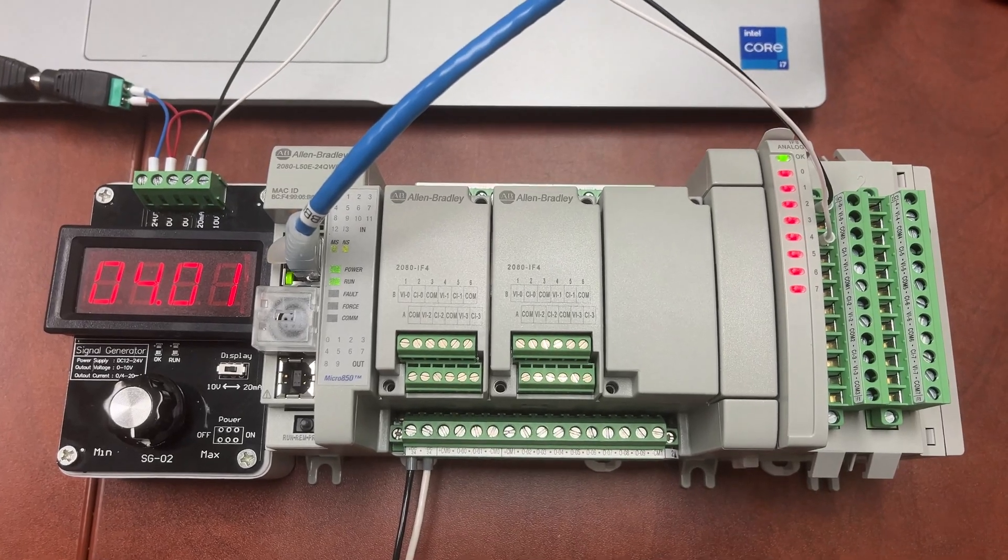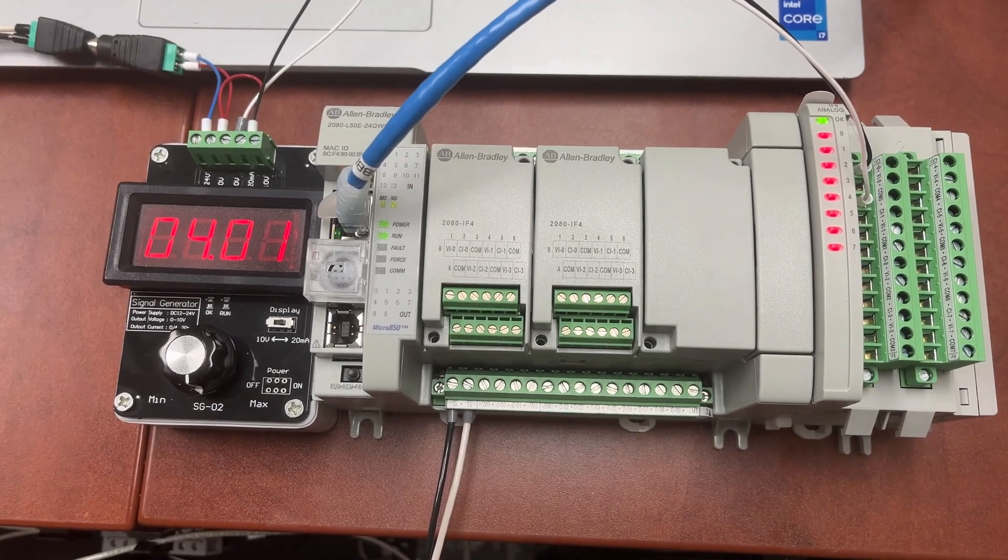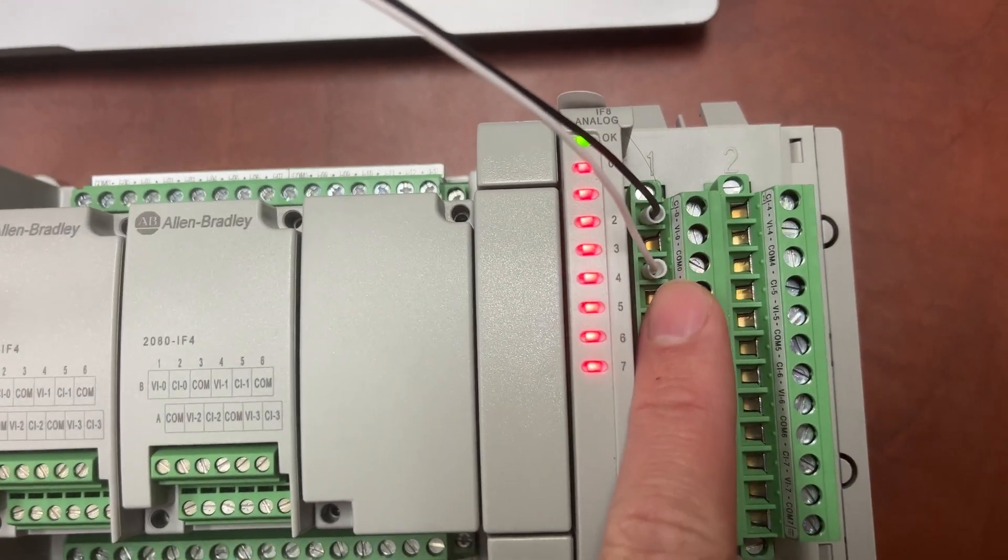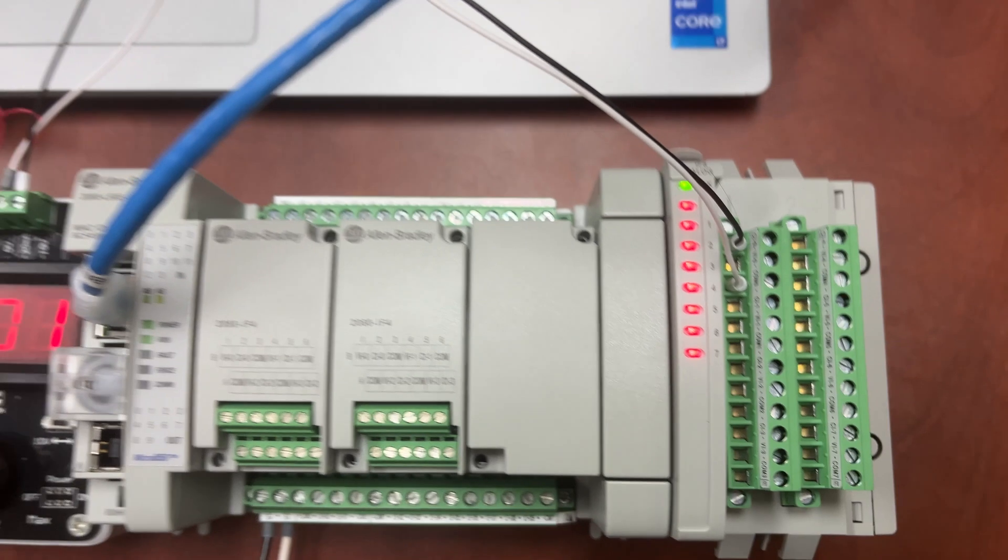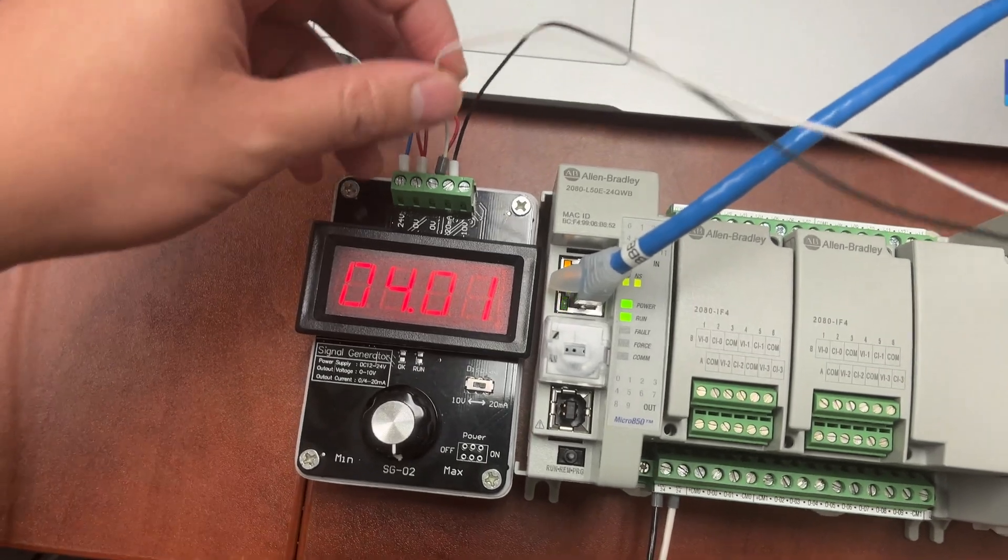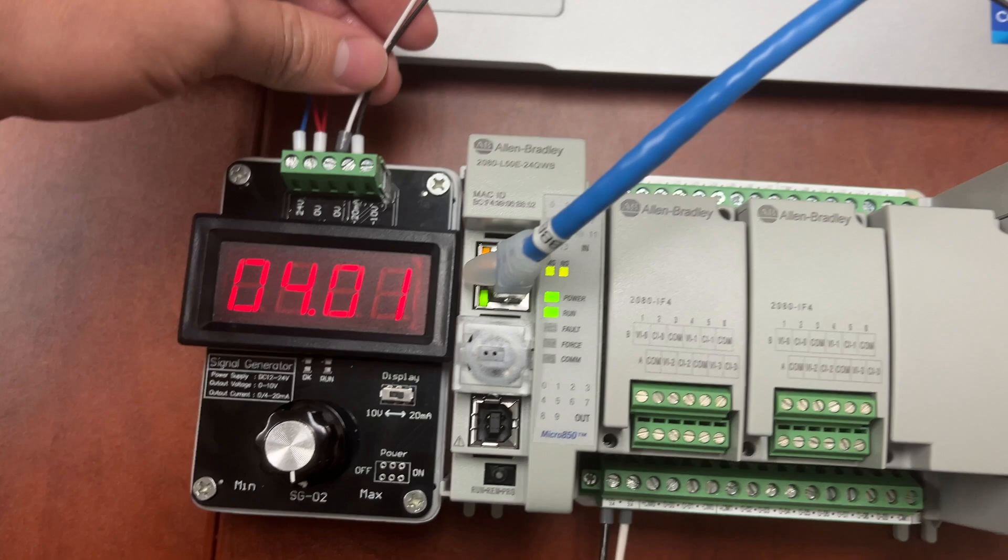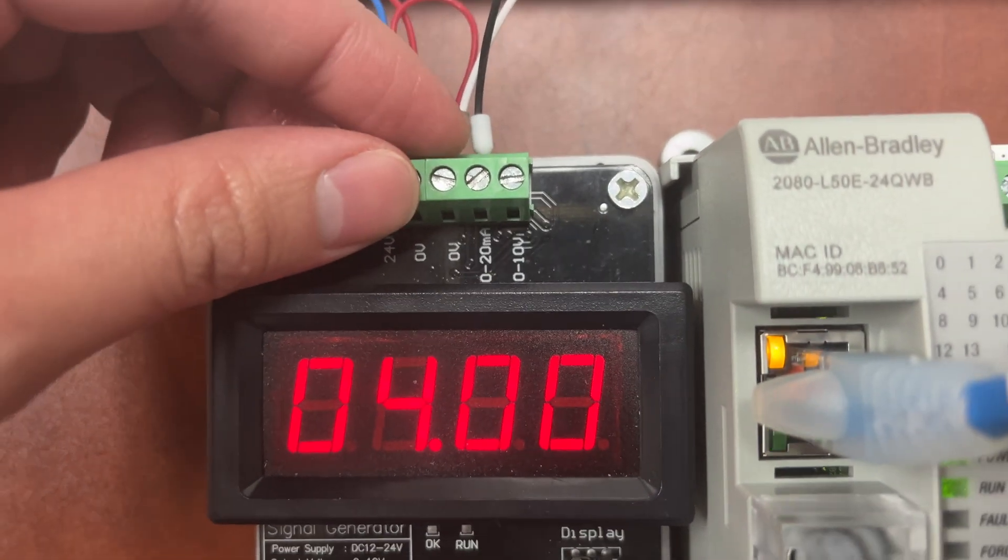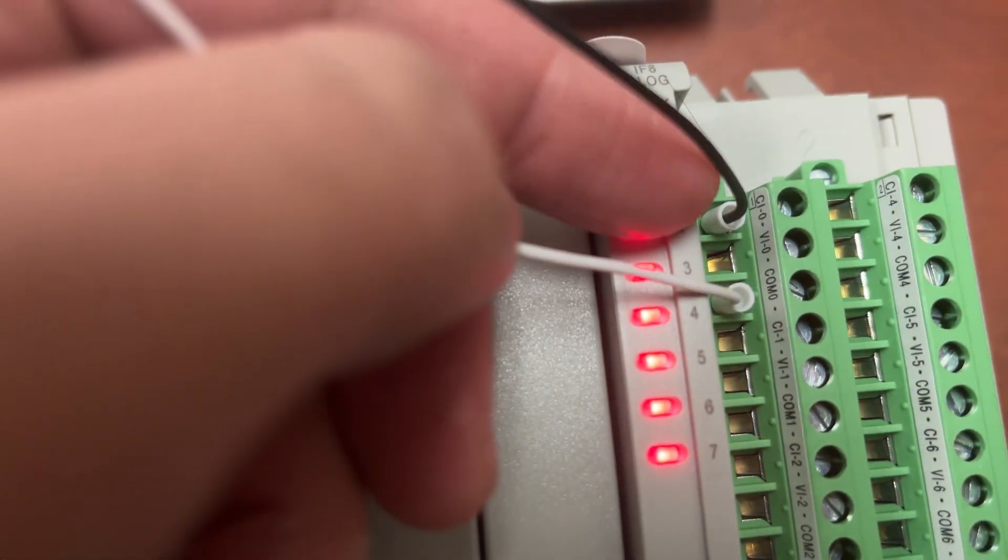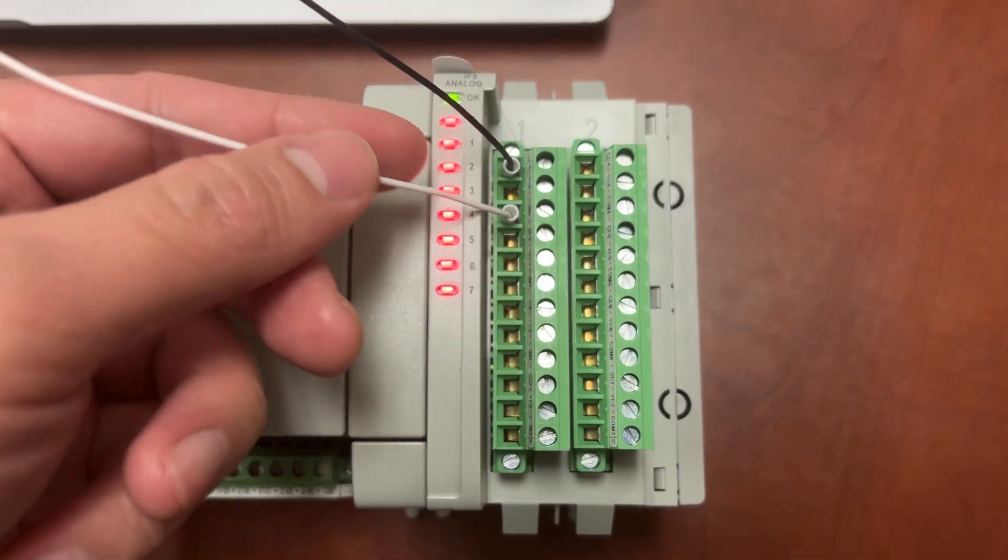Now let's check the range for the PLC tag for the analog input channel 0 on the first expansion module 2085-IF8. We have the white wire for 0-volt from the simulator wired to COM0, and the black wire for 20 milliamp on the simulator wired to CI0, current input 0 on the expansion module.